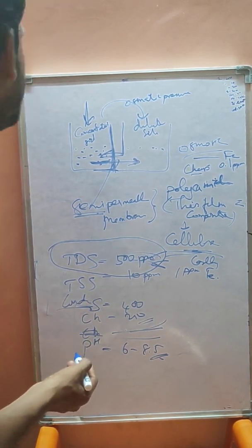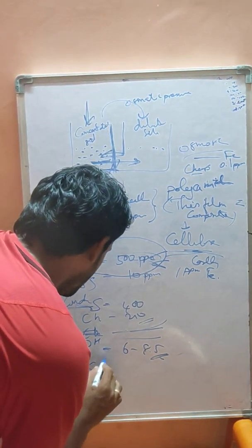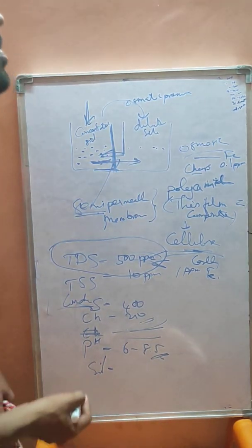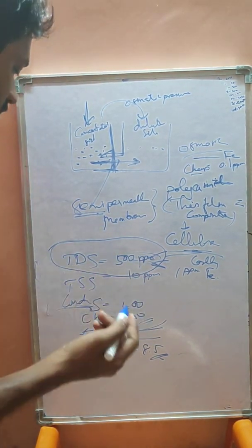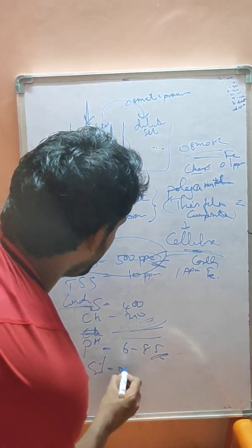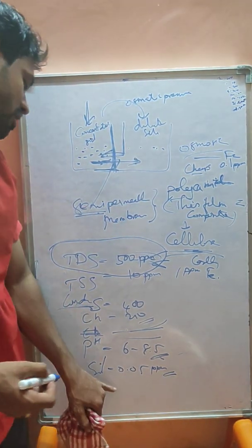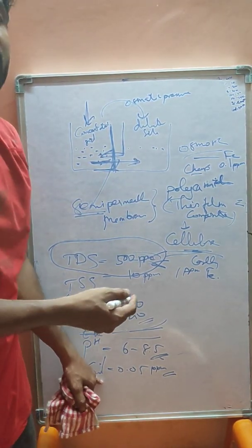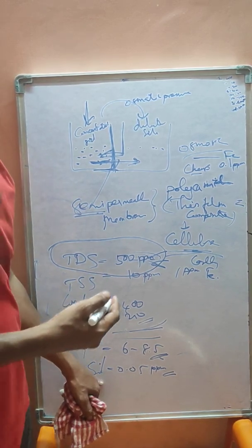And silica content is also very important, because this RO water will be used for producing DM water. So that should be less than 0.05 ppm. The silica content mostly will be removed in the RO plant only. It cannot be removed much in the DM plant.